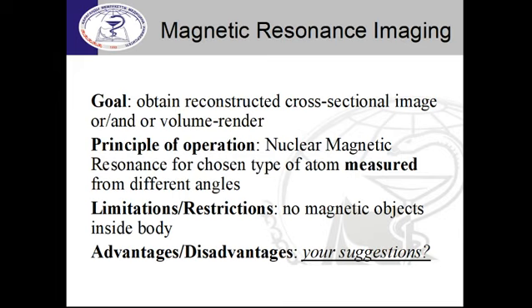If metallic objects with magnetic properties are present inside or near the human body — especially artificial pacemakers, electronic or magnetic implants, or even primitive metallic components in bones — they become a problem. In the applied magnetic field, these objects will try to move and overheat, which can bring pain to the patient. Such persons must totally avoid this technology. This is a restriction, not merely a limitation — you cannot perform this test for such a patient, as it would bring suffering, injury, or worse.